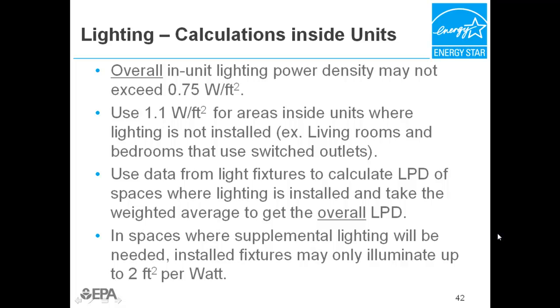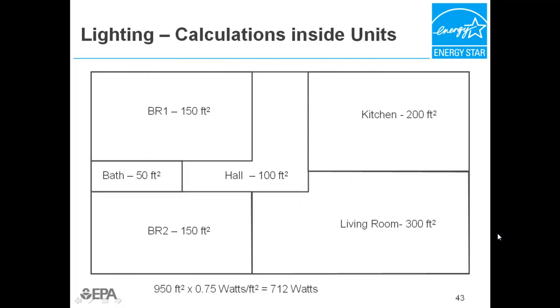In spaces where some fixtures are installed, but occupant-provided supplemental lighting will be needed to meet foot candle requirements, the fixtures that are installed by the builder may only account for illuminating up to 2 square feet per watt installed. This floor plan is not drawn to scale, but demonstrates the calculations. The total square footage of this apartment is 950 square feet. If providing lighting in each space that will fully provide illumination without the need of any supplemental lighting, no more than 712 watts may be installed if following the prescriptive path.